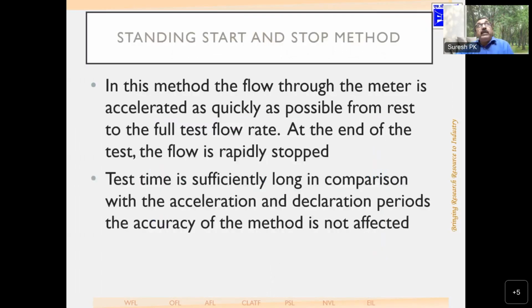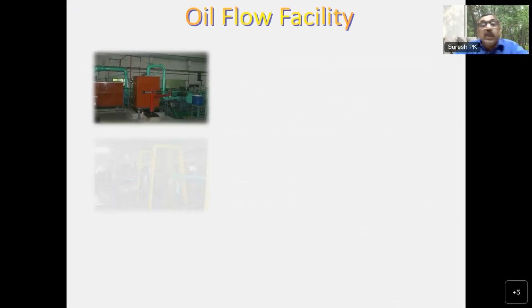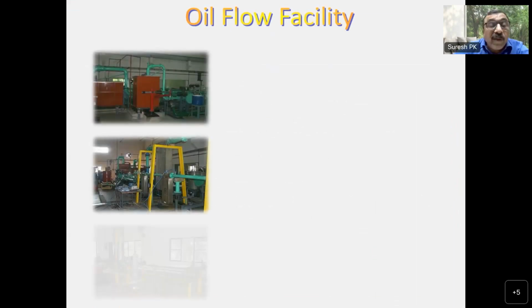Now you have another method called the standing start and stop method. In this method, the flow through the meter is accelerated as quickly as possible from rest to the full test flow rate. At the end of the test, the flow is rapidly stopped. That is, whatever is coming through the meter is directly going into the weighing tank. There is no diversion involved in this. The test time is sufficiently long in comparison with the acceleration and deceleration periods, so the accuracy is not affected. The oil flow lab uses this particular method.